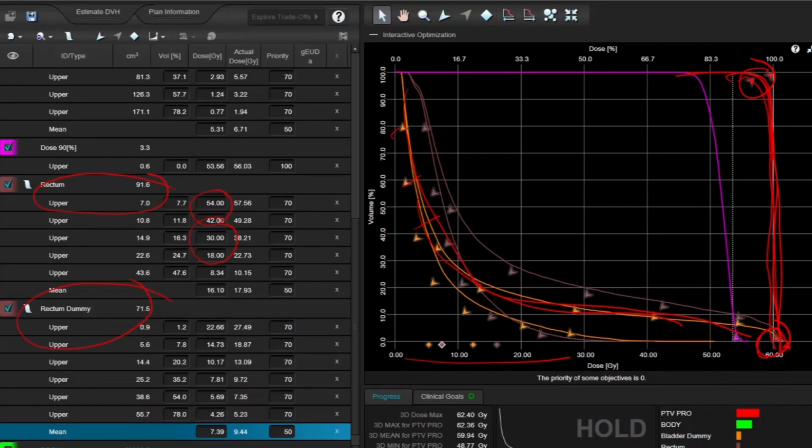Optimization is nothing but the process of forming small segments. So the optimization algorithm is also different from the dose calculation. Once you have achieved your desired objectives in this optimization window, you need to go for the dose calculation. In optimization, I told you that it performs only photon fluence. So this photon fluence needs to be converted into the dose distribution. For dose distribution, an independent algorithm is required, which we call the dose calculation algorithm.